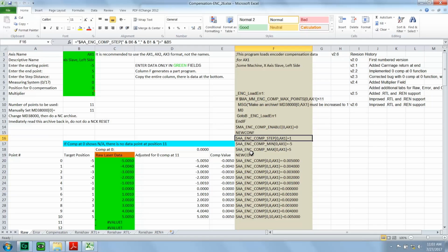So, for example, if we calibrated the machine in January, everything was good, we've got a good count file, we've got that saved. We recalibrate in March because that's our schedule. Everything's fine. We recalibrate in May, everything's fine. But then we find out that we'd somehow started making bad parts in April. What happened? We look in the comp files and compare the March file versus the May file, and we see that all of a sudden there were some grossly different numbers. If you had kept these files, you'd be able to do that. It's a choice, not necessary. It depends on what your shop decides to do.